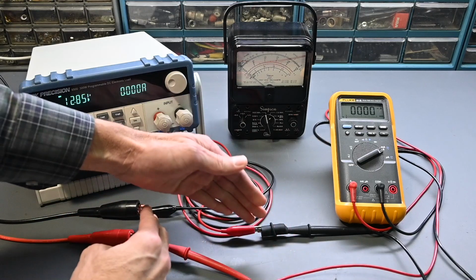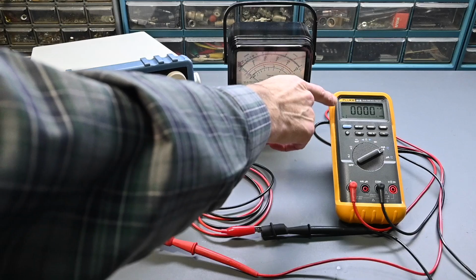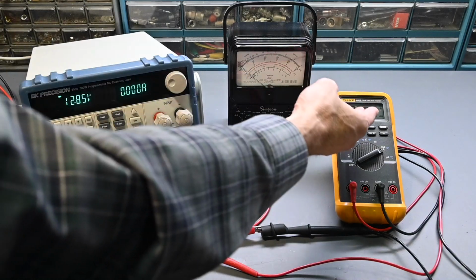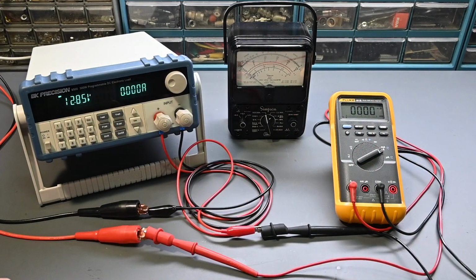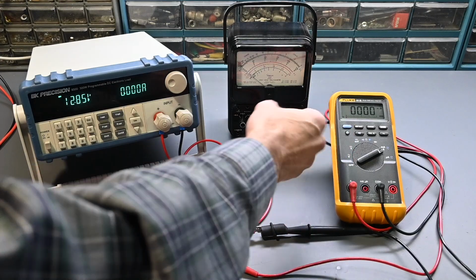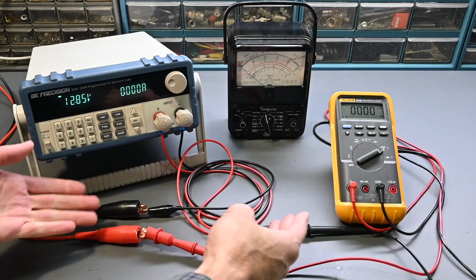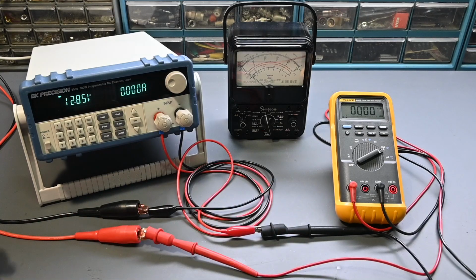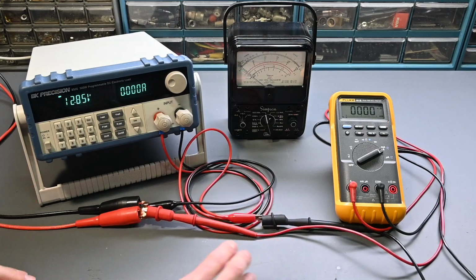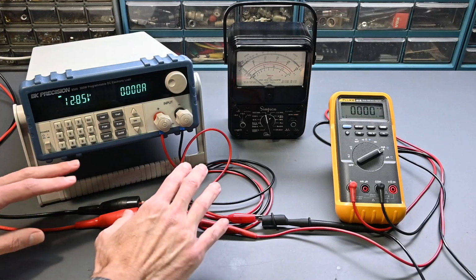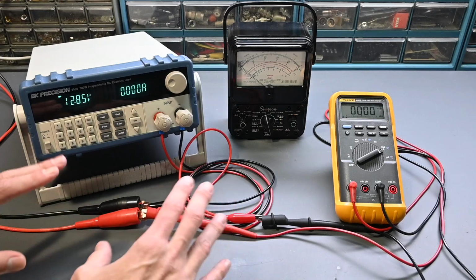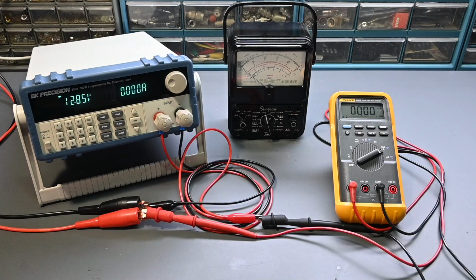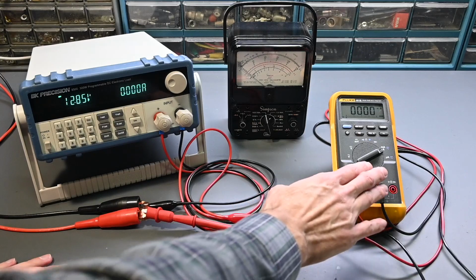If you reverse the polarity of these test probes, you'll end up getting a negative symbol on the display. The actual current measurement won't be affected. But if you're concerned about showing positive or negative current flow and you want that display to be correct, then again, this is the correct polarity on the test probes. All right. And also, if you don't know the current level that you're going to measure, and you're not exactly sure how much current is going to flow, always start with the highest current measurement settings on your meter.